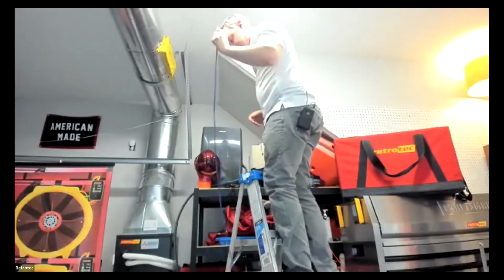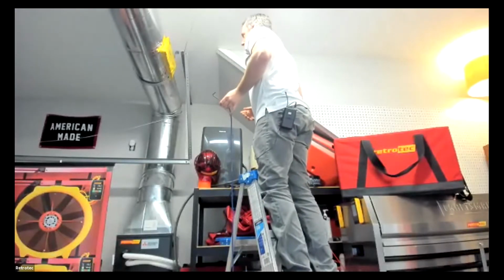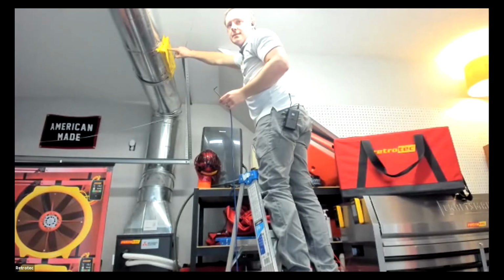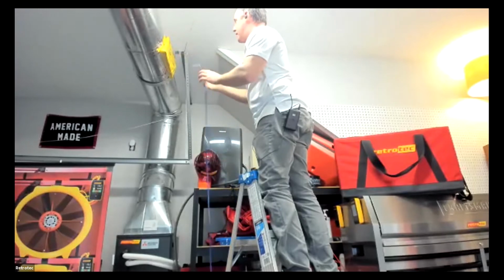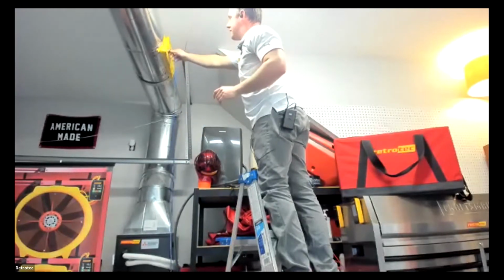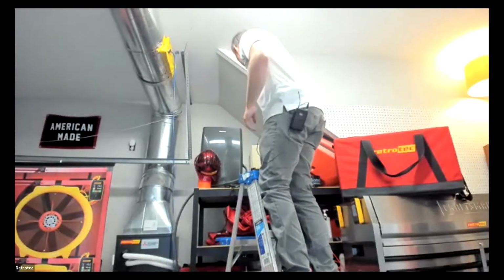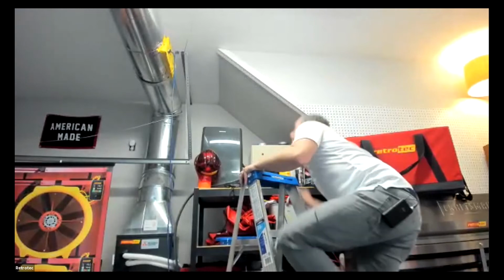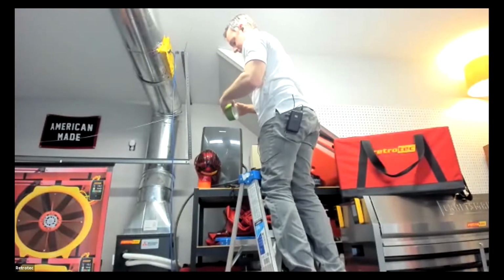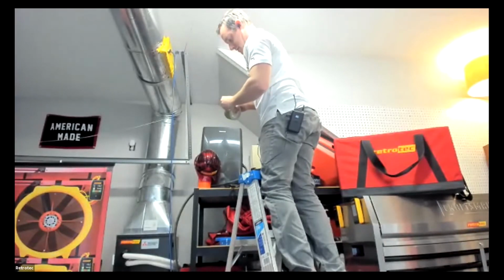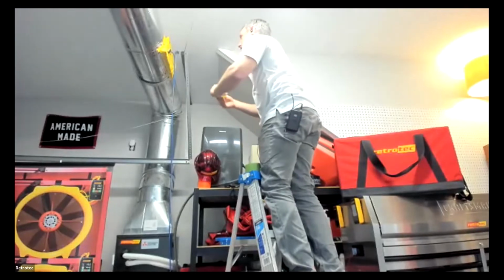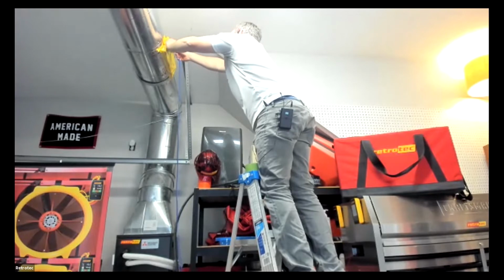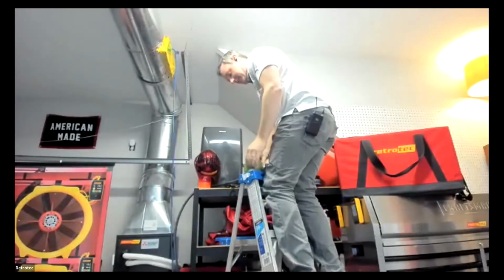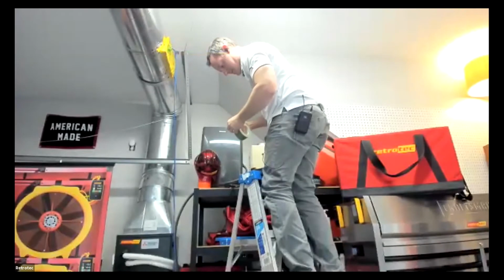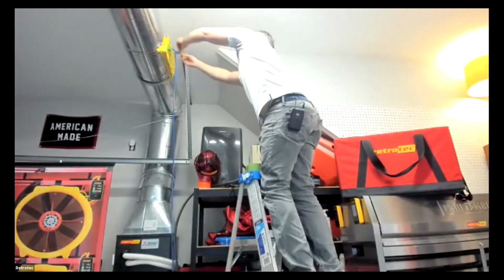Now, the next thing we want to do, there's some perforated edges there. And so we just want to poke a hole there with our finger. And then take this static pressure probe and pop it in like so. And if you notice, some of them have a magnet that can kind of help hang it on. Sometimes it's not enough. But we've made a hole there in the system. So what we want to do is grab some painter's tape and just give it a little extra support. So just a little piece on one side to hold that on. So you're holding that static pressure probe there in place, and you're sealing up that hole at the same time. And there we go.